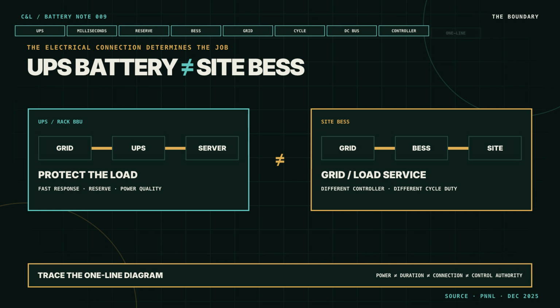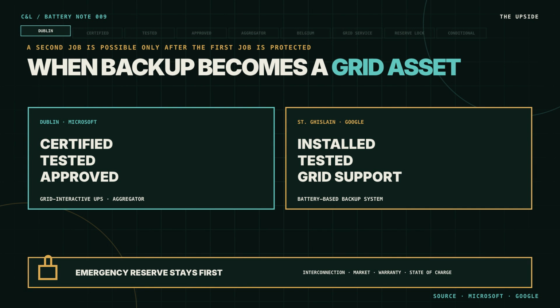The practical lesson is simple. Megawatts measure power. Megawatt-hours measure duration. Neither number tells you which bus the battery connects to, what controller has authority, or whether the IT load remains protected during a grid event. Before valuing a battery, trace the one-line diagram. The electrical location can matter as much as the chemistry. There is real upside when the contracts and controls allow it.